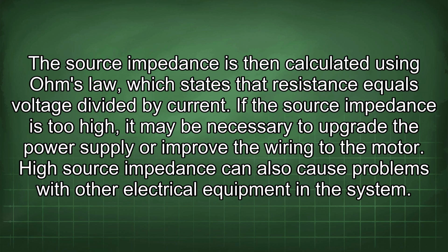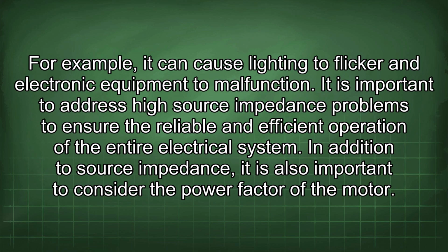to the motor. High source impedance can also cause problems with other electrical equipment in the system. For example, it can cause lighting to flicker and electronic equipment to malfunction. It is important to address high source impedance problems to ensure the reliable and efficient operation of the entire electrical system. In addition to source impedance, it is also important to consider the power factor of the motor.